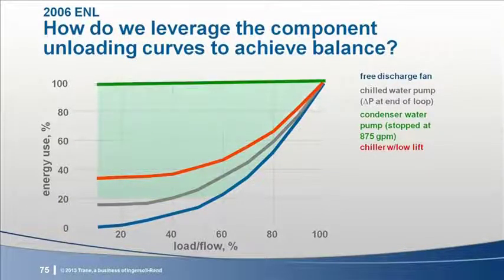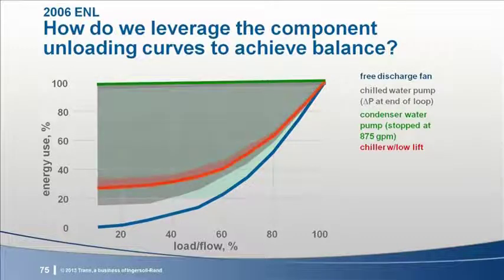Such operation would result in the fans and pumps running at 100% speed at most conditions. The pump and fan power would rise significantly relative to the system load. The result is that the chiller condenser would get a higher flow of cooler water, which would reduce the compressor's lift and energy use. The question is, what would happen to the system energy use? Past analysis has provided this answer. The system power would go up, in typical cases between 5 and 10%.